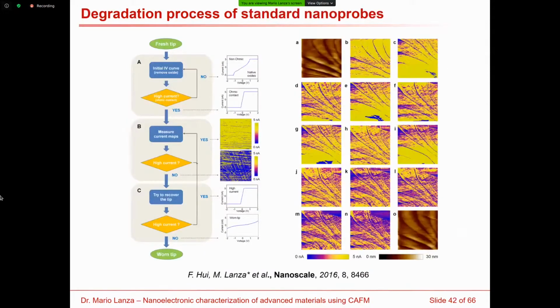So we evaluated the degradation speed of one standard conductive AFM tip. We developed one method based on an initial check of the conductivity, a sequence of current maps at a constant force and voltage, and another check of the conductivity of the tip. And we observed that for one specific tip, one specific sample, and one specific set of measuring conditions, our tip degrades in 13 scans. It was very obvious because initially the scans show a lot of current, which here is indicated with yellow color. And after just 13 scans, the image turns blue, which means we are not measuring enough current.